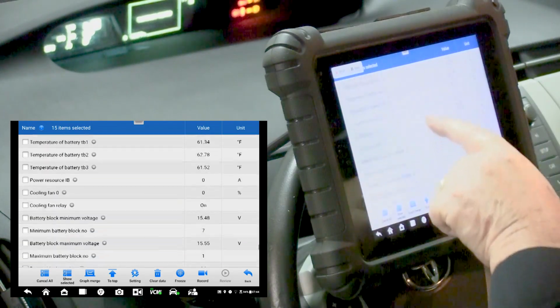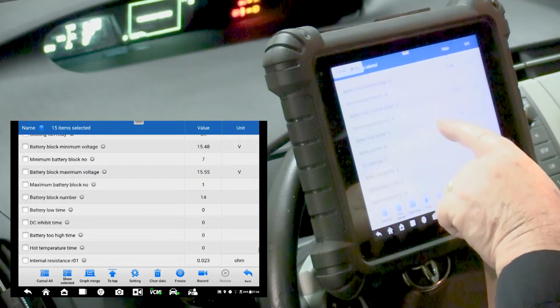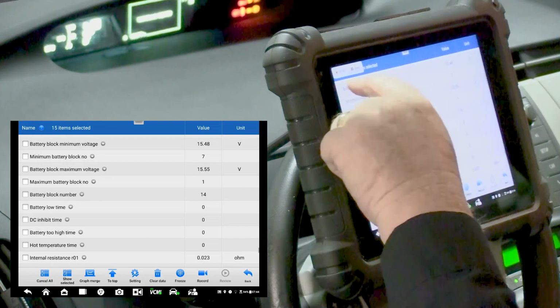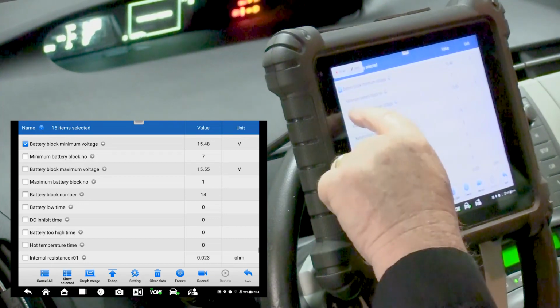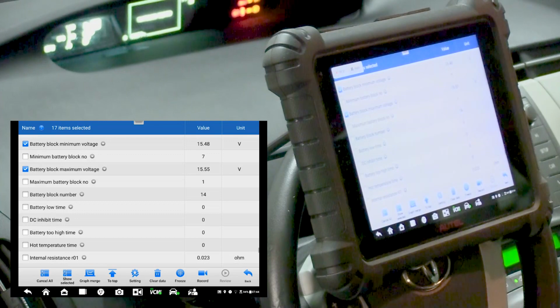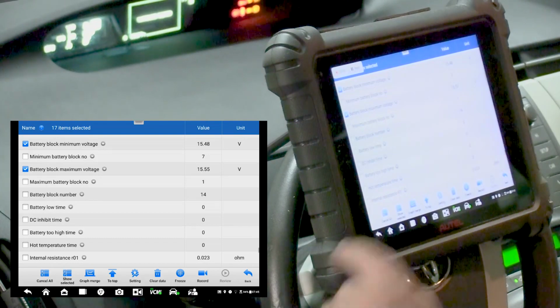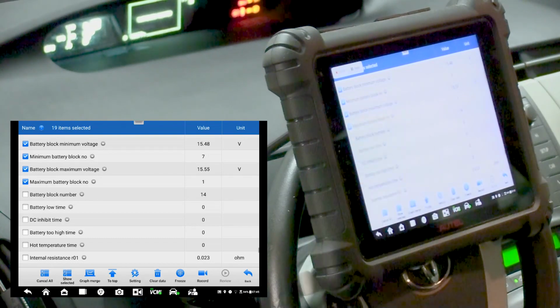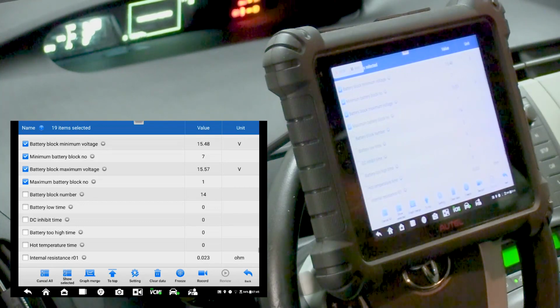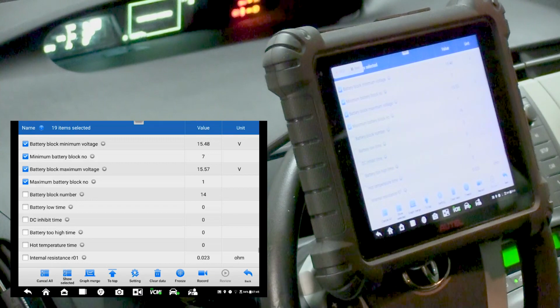There's some other PIDs we want to take a look at, right here — battery block minimum voltage and battery block maximum voltage. You can see it ranges just what we looked at for the variance, 15.48 minimum, 15.55 maximum voltage in the cells. We're going to take a look here at the maximum and minimum battery block numbers. In this case, the block with the lowest voltage is block number 7, and the highest is block number 1.